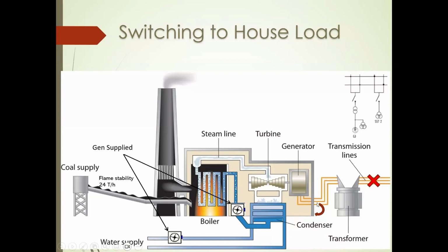Now, what you have to understand is that when you operate this, if you want to take this unit into house load mode, essentially your connection to the grid is severed. The generator has been generating 300 megawatts. Now only these two pumps and other auxiliaries will work, and that's about 15 megawatts, almost 5% of the rated generating value. So that's almost a full load rejection.